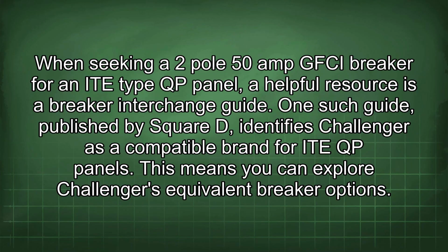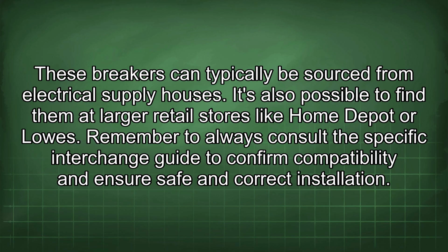When seeking a 2-pole 50-amp GFCI breaker for an ITE Type QP panel, a helpful resource is a breaker interchange guide. One such guide, published by Square D, identifies Challenger as a compatible brand for ITE QP panels. This means you can explore Challenger's equivalent breaker options. These breakers can typically be sourced from electrical supply houses. It's also possible to find them at larger retail stores like Home Depot or Lowe's. Remember to always consult the specific interchange guide to confirm compatibility and ensure safe and correct installation.